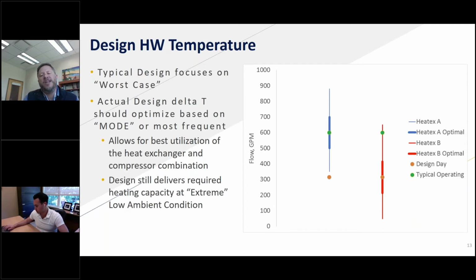We're really designing a system that's not as efficient or effective as it should be, versus if we design the system, like I said, for that mode of operation, we're actually looking at a higher ambient temperature. And when we do that from a design standpoint, we set the flow rate, we set how we're going to pump things at that higher ambient temperature. It puts us in a much better spot from an overall system efficiency.